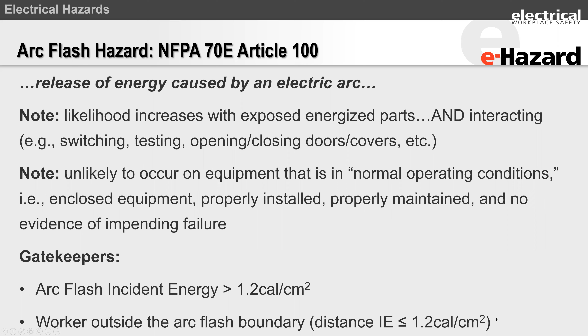I thought I would put out a picture and a video here to explain what I'm talking about. If you see a sticker on a piece of equipment that says the energy is greater than 1.2 calories per square centimeter, you are going to require arc-rated clothing, and that means head-to-toe protection. Just giving somebody arc-rated clothing and not expecting them to use any hand protection or head protection is not going to cut it. Hugh Hoagland is going to speak about this in a little while. And here's a brand new video that we've just worked on recently, compliments of Arcwear and Kinectrics. Hugh can speak about this a little bit more.